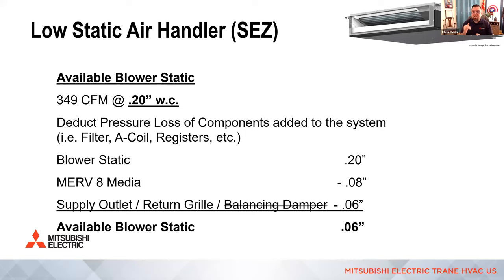Also, we need to deduct for 1 supply register, 1 return grill, and if you have a balancing damper, then you would deduct for that too. And this is just a standard of 0.03 each out of Manual D. It's a standard amount if you use a normal, let's say, Hart and Cooley register, not the Regio register, the crazy ornamental wooden ones. Obviously, that's more restriction, all right? But if you're using something standard, you can just adjust for one supply register and a return grill.